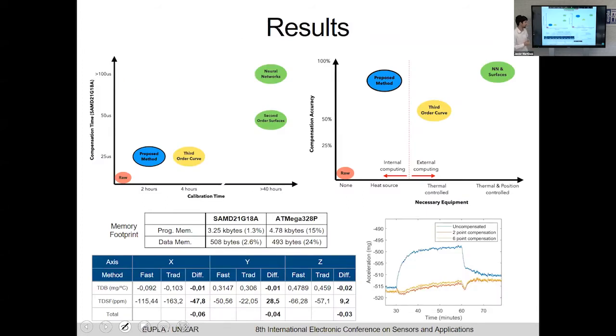Comparing this technique with other traditional techniques, our calibration time is reduced to only 2 hours after the device is powered up. If the device has already powered up, the calibration time can be 1 hour and a half. Also, the compensation time in the microcontroller tested is only 25 microseconds. Other traditional technologies require up to 40 hours or more to obtain all the necessary data for the polynomial fitting. And during the compensation phase, they also require more time.